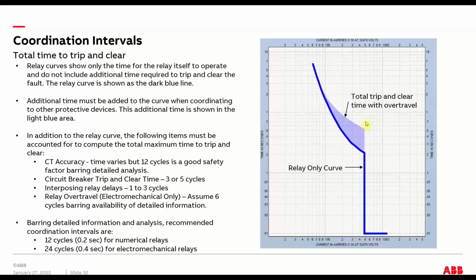set your next breaker. So your next breaker couldn't be anywhere except above here, or else you wouldn't be fully coordinated. So in other words, you couldn't just draw the next breaker's curve right down this area, intersecting this hatch, because you would run the possibility of tripping both of them at the same time. They wouldn't be coordinated. And here's a couple really, really rough recommended intervals.